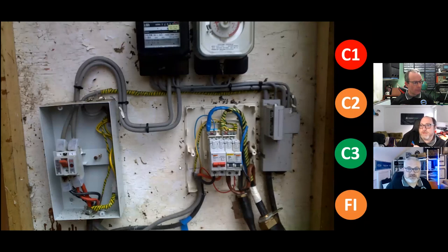Just moving on to the next one. Yep. Look at this dog's dinner. That was actually found, so excuse me. For anyone who's not aware, there's an old meter on the top. I think it was an old ABB one or Sangamo one. And the thing next to it is the old time clocks, which used to take their feed off the meter and then switch out a little contact in the meter and give you two rate systems. That's how that was found.